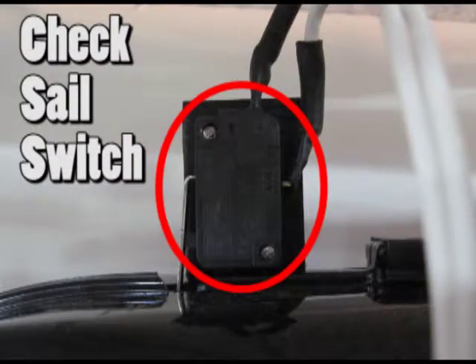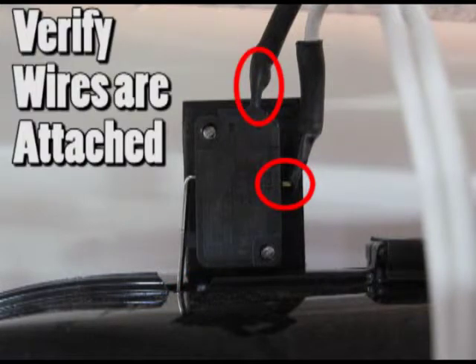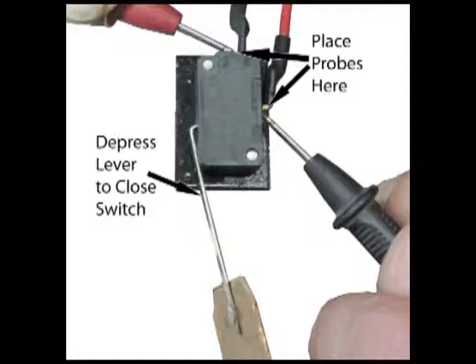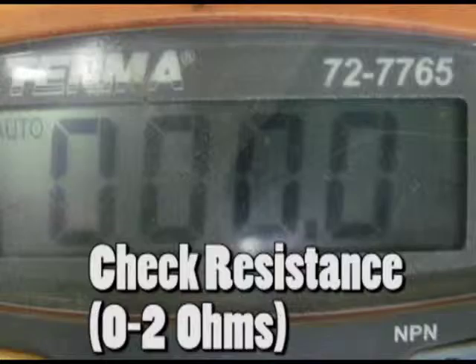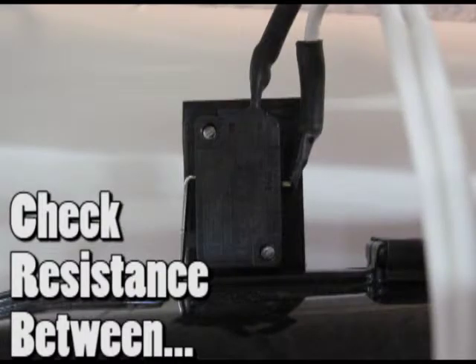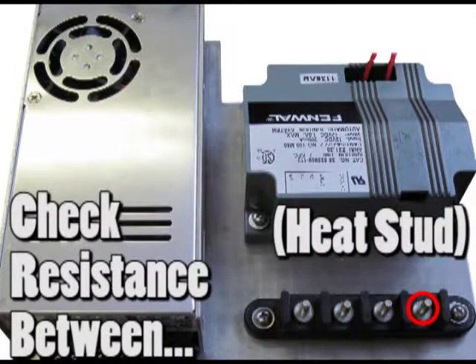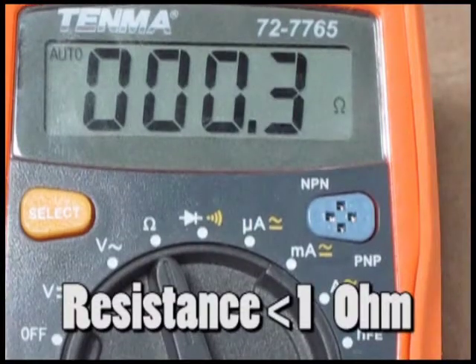Check the sail switch on the blower. First, check that the wires are attached. With the power to the heater off, check the resistance using a multimeter between the 2 terminals on the sail switch with the activation lever depressed. The resistance measurement should range from 0 to 2 ohms. Also check the resistance between the rightmost terminal on the sail switch and the heat stud, the rightmost stud on the 4-post terminal block. Resistance should be less than 1 ohm.